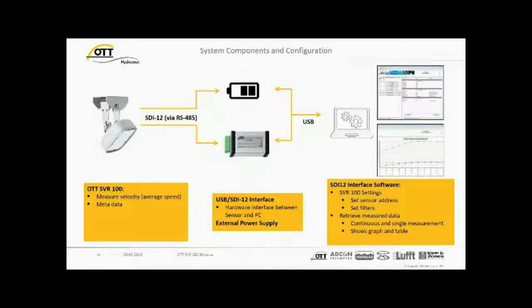If you want to just communicate with the SVR100, you can take the USB SDI12 interface we provide. This is a small gray box here in the picture, and you take the SDI12 interface software, and then you can connect via the small box to the sensor. You can do settings, you can set filters, you can check anything of the instrument, and you can also start continuous measurements, single measurements, and show graphs and tables. This is possible if you just want to communicate with the sensor.